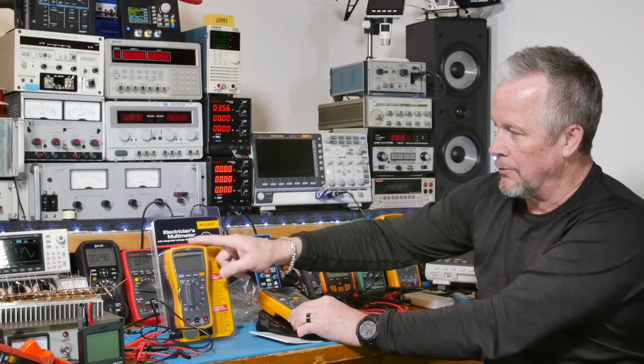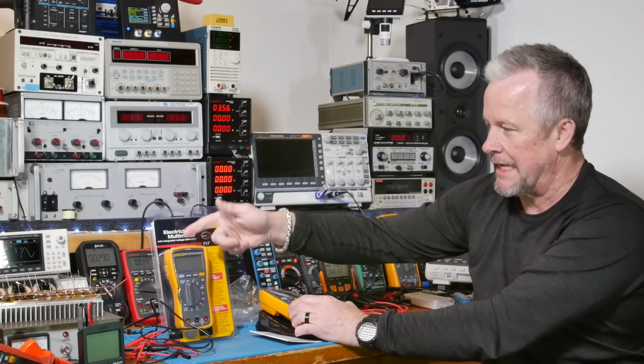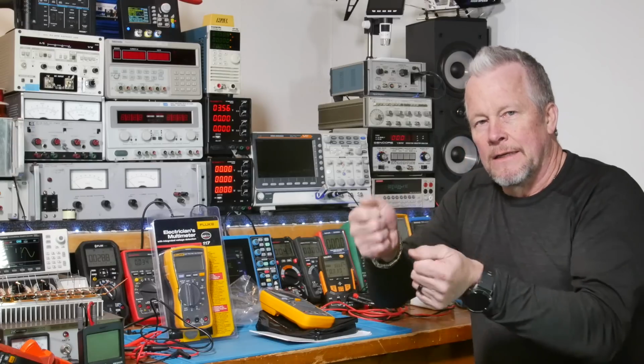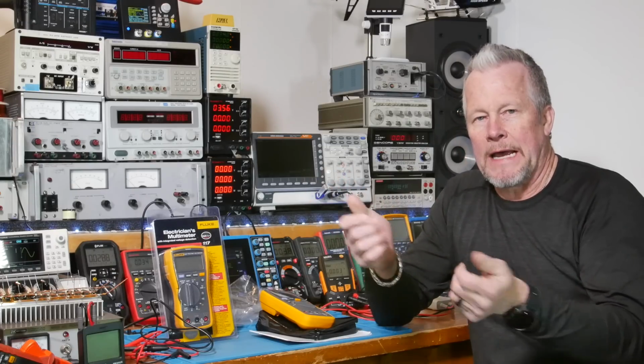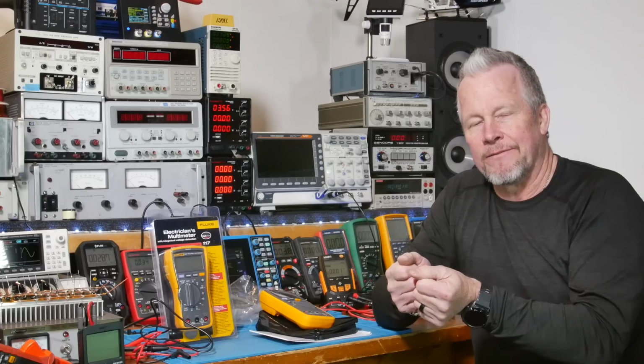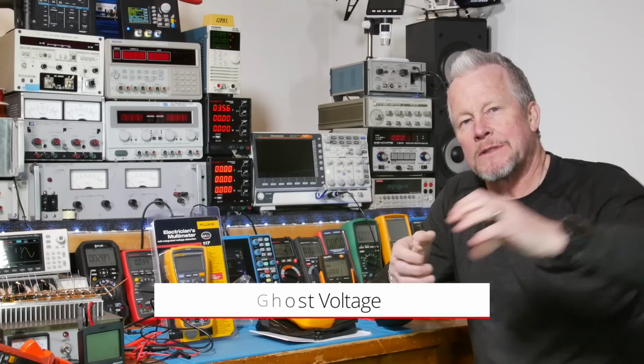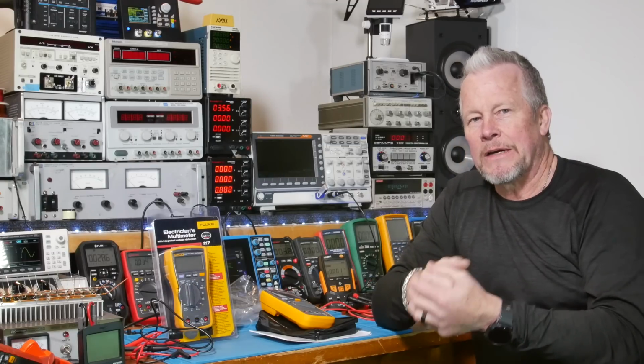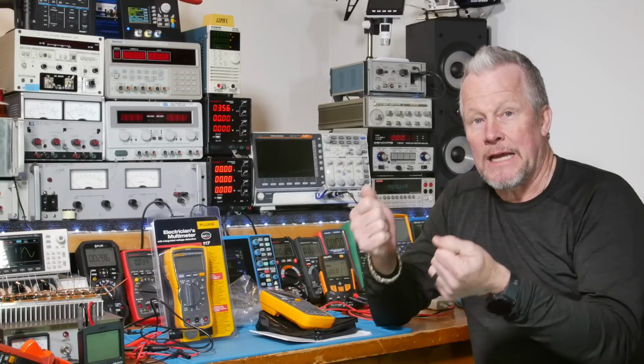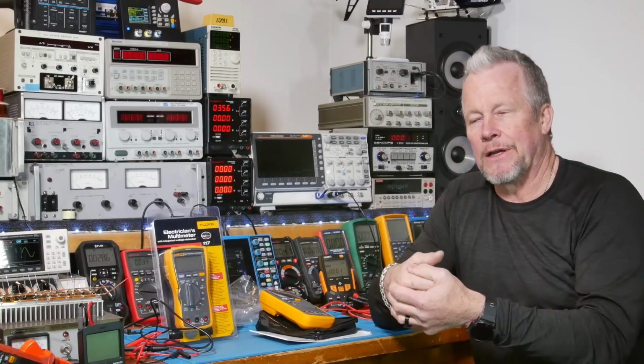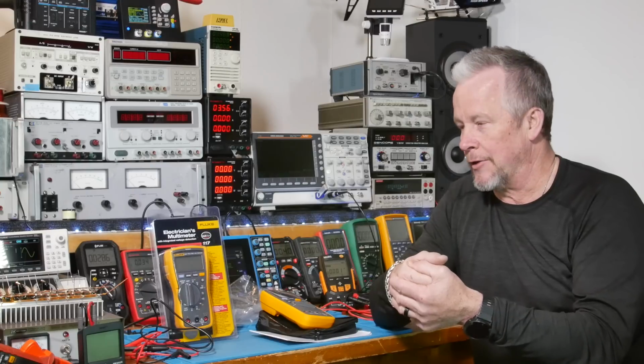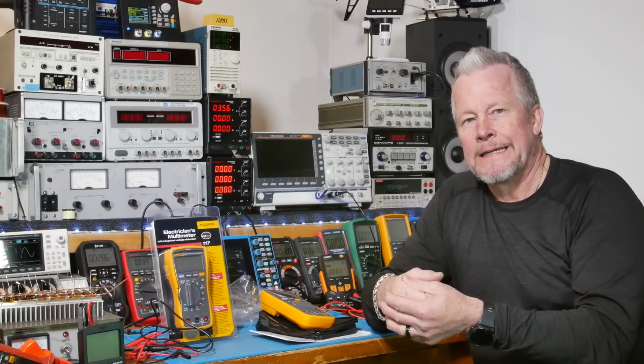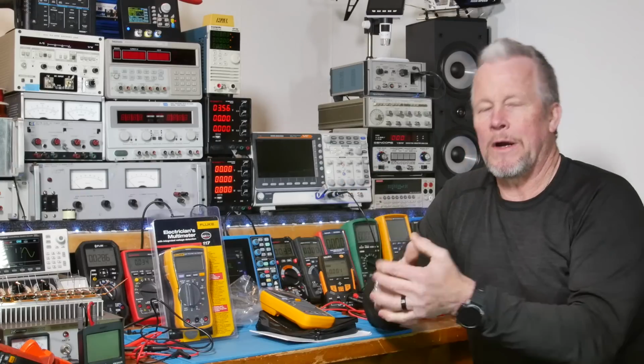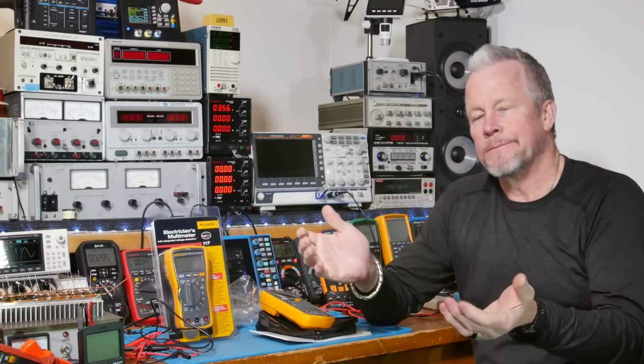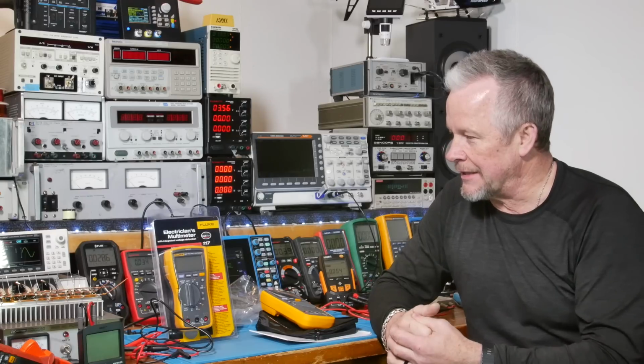Now this guy has a low Z setting, an auto V slash low Z setting. If you're testing a cable that has some voltage on it that shouldn't, but it's running in a bundle with other cables, those other cables could be energizing it with very low energy. Your meter, being high impedance, might see some voltage there and fool you a bit. But if you switch to low Z, it doesn't take much impedance to drain that low energy off the cable, and you'll see it read 0 volts.